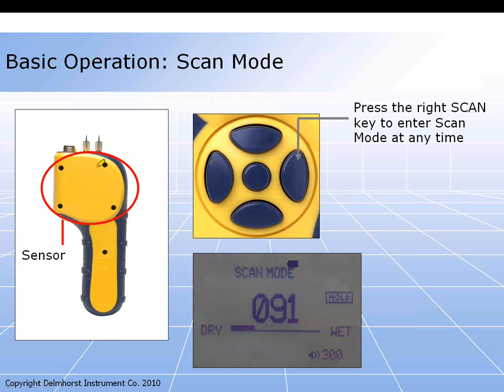But if you change the angle at which you hold the meter against the material you're testing, the readings change. So we felt a flat back gives more consistency in the angle and pressure you're applying to the surface.